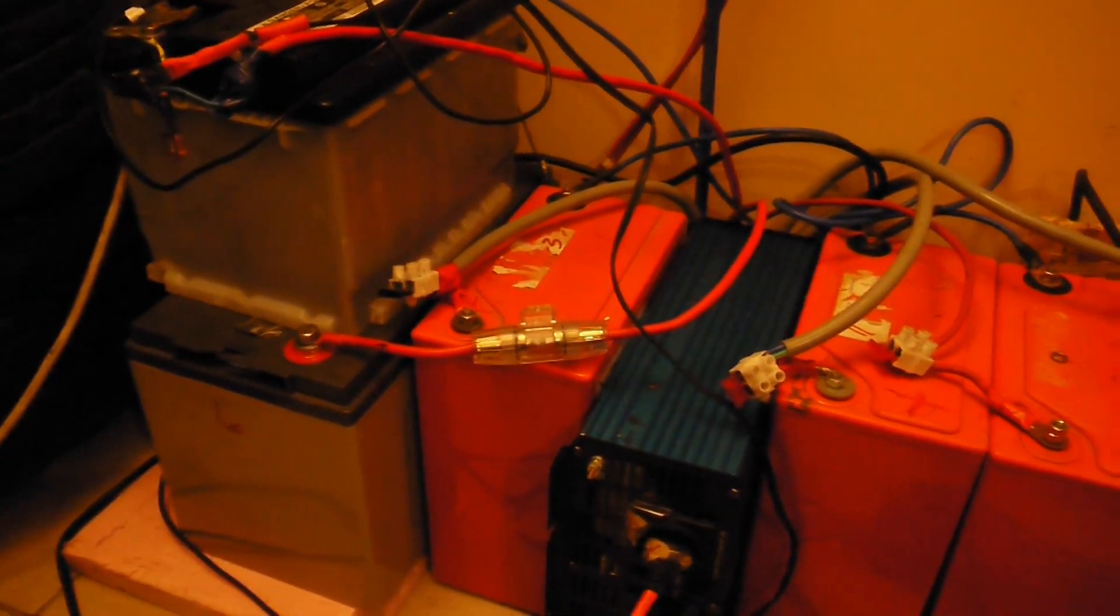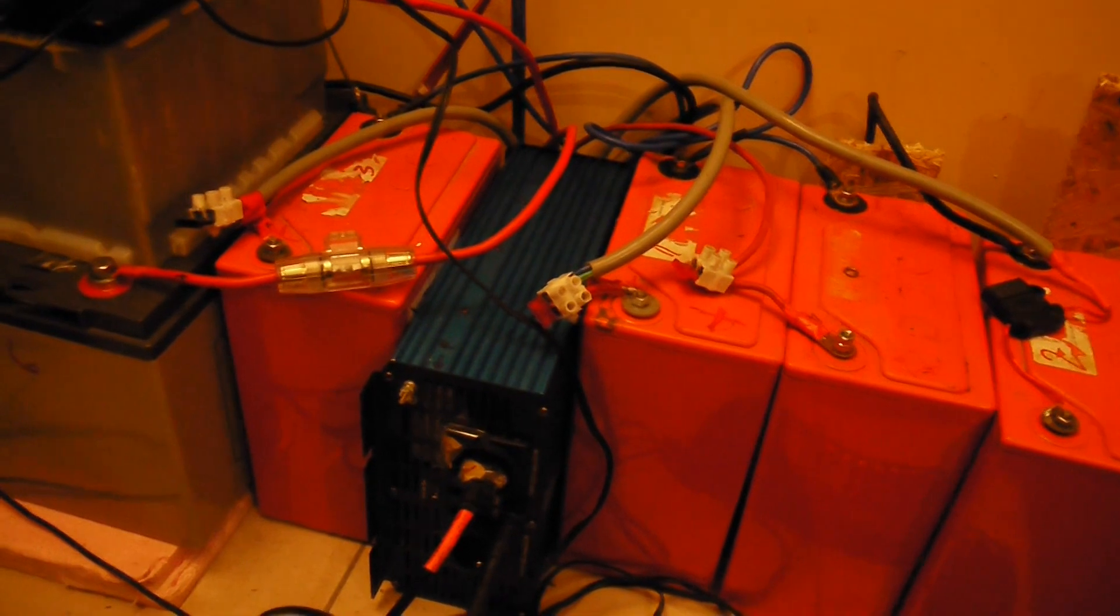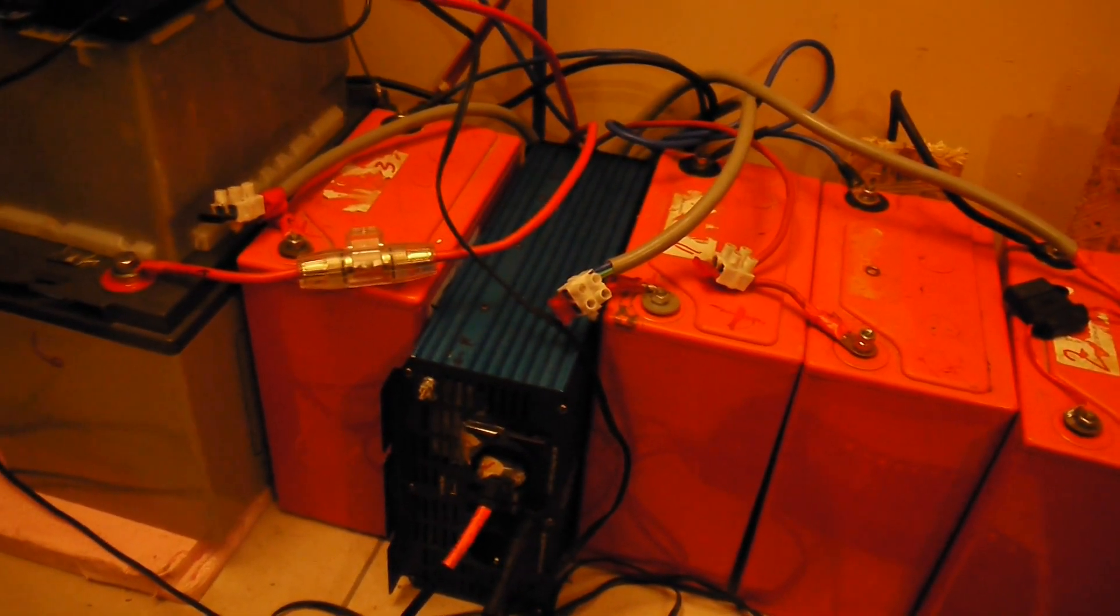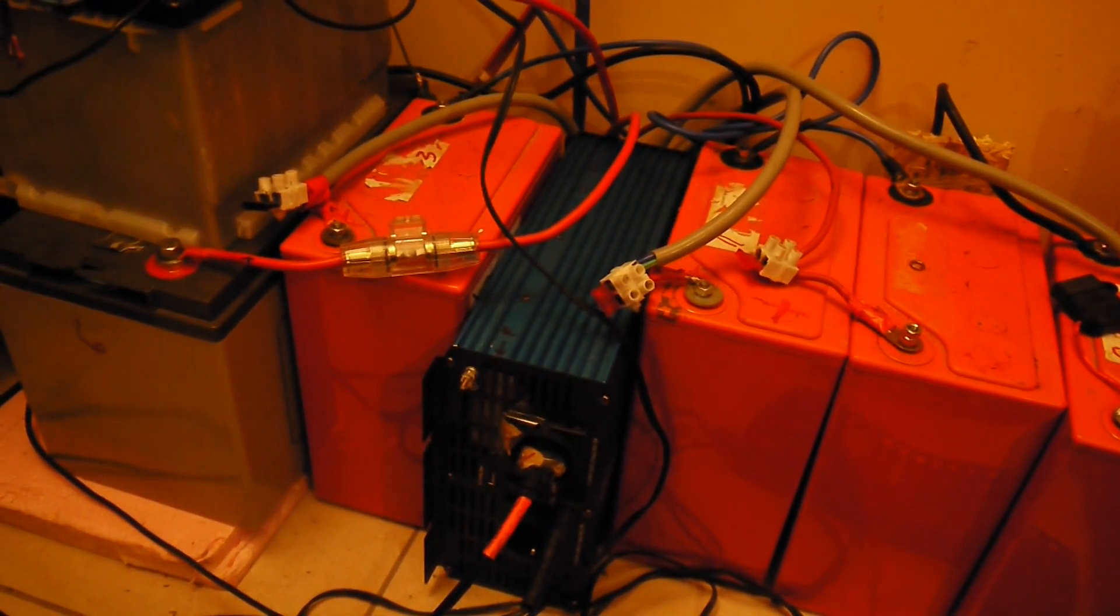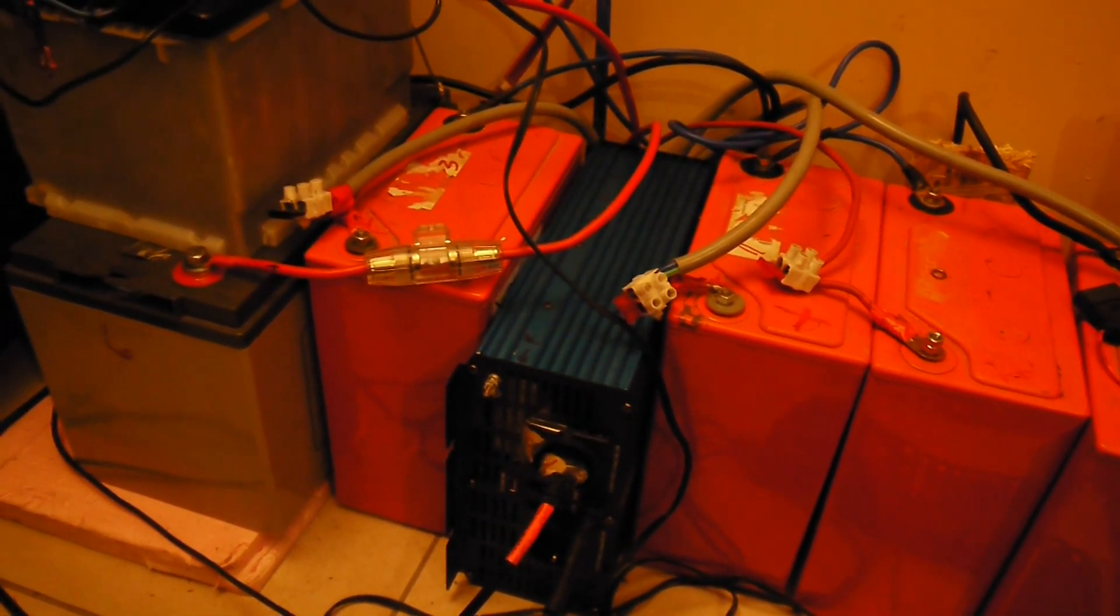A kind of advice I have for everybody looking at my tutorials: don't forget to fuse every little battery or echo you are having in this solar ring, because it's really dangerous. Just in case, if you have a short somewhere, one of the cells or batteries getting in short, all the others are protected and the main thing is protected too.